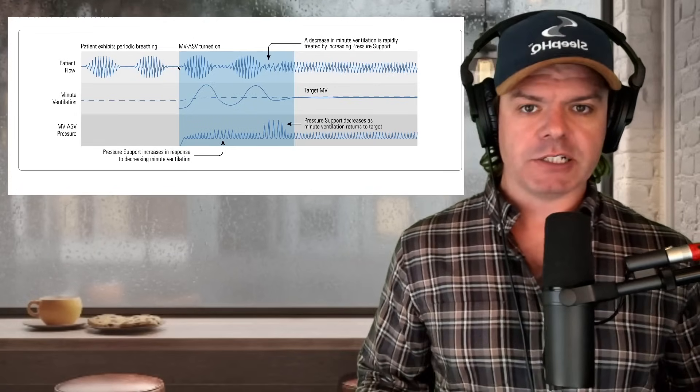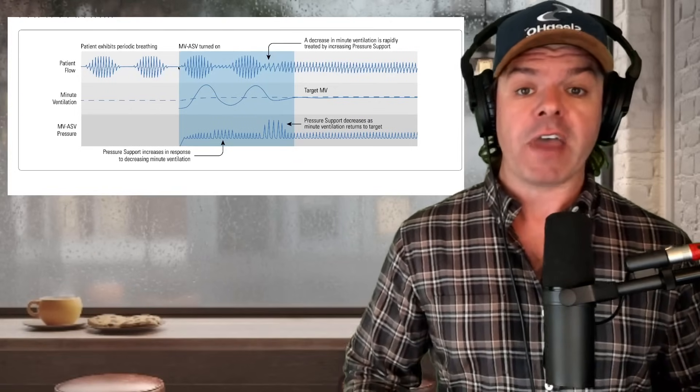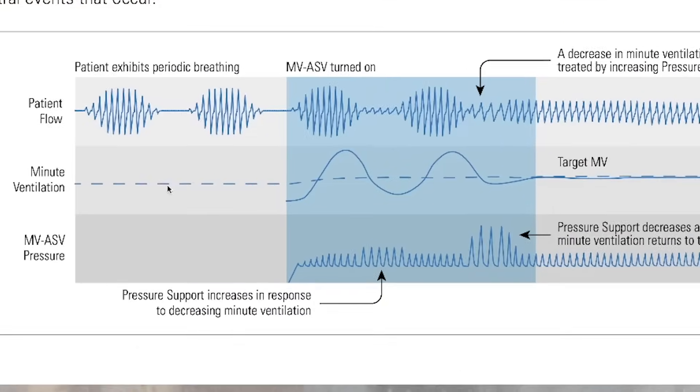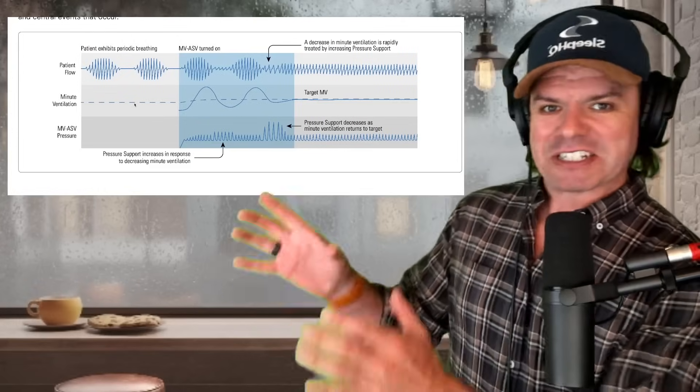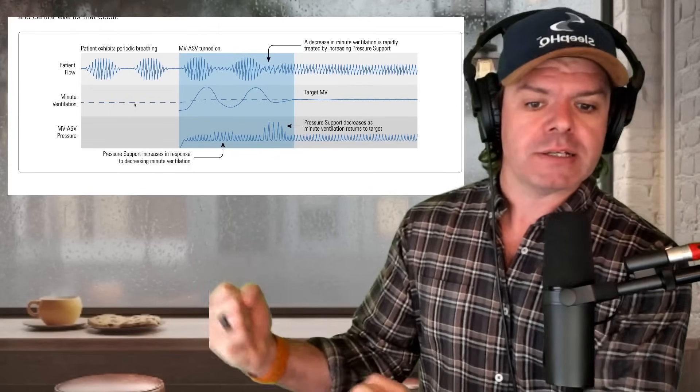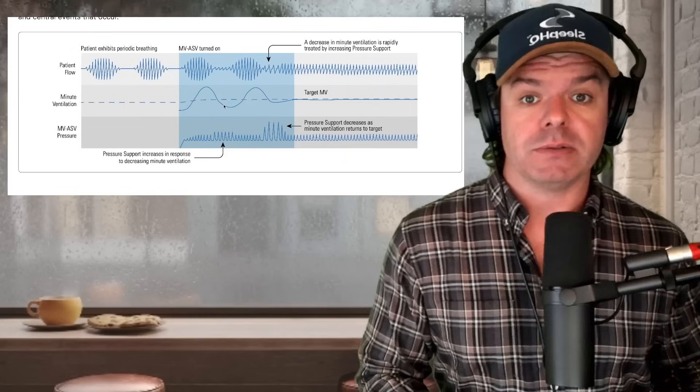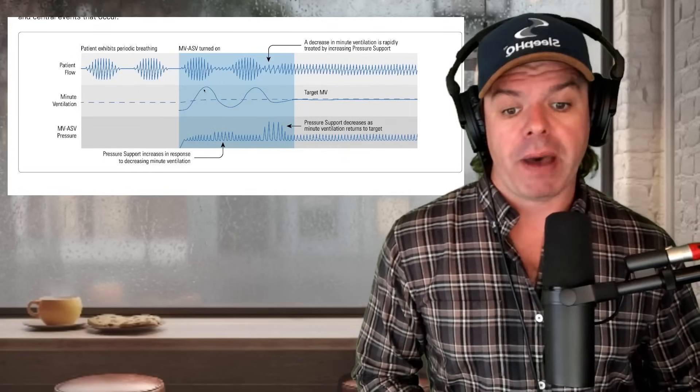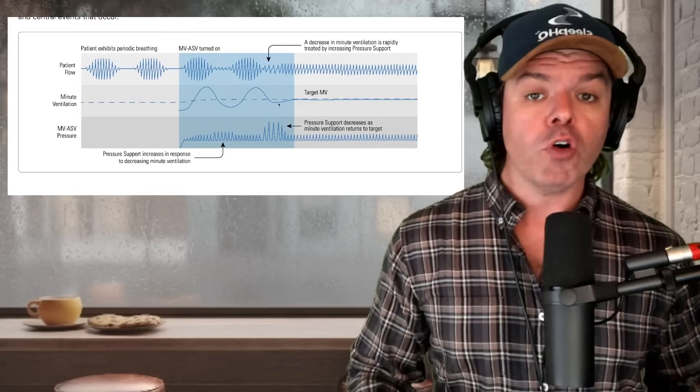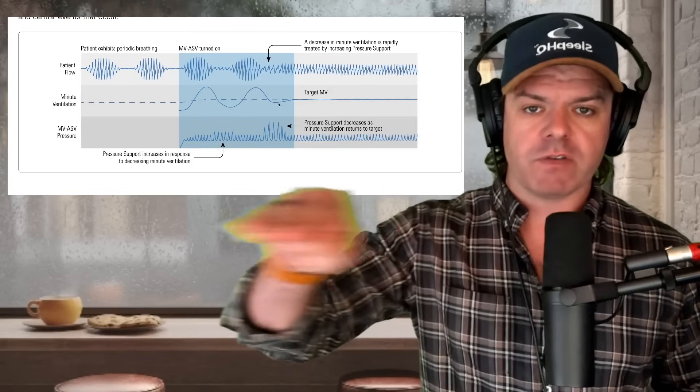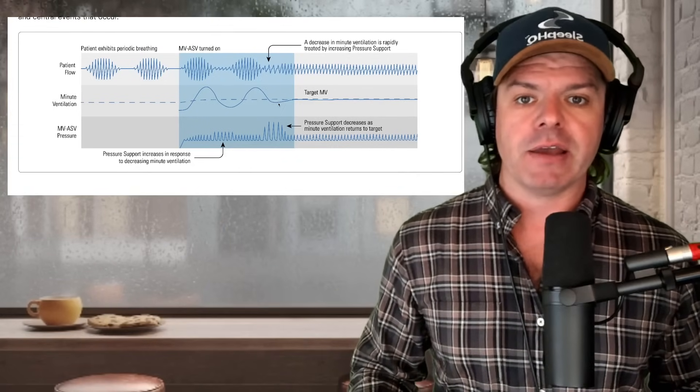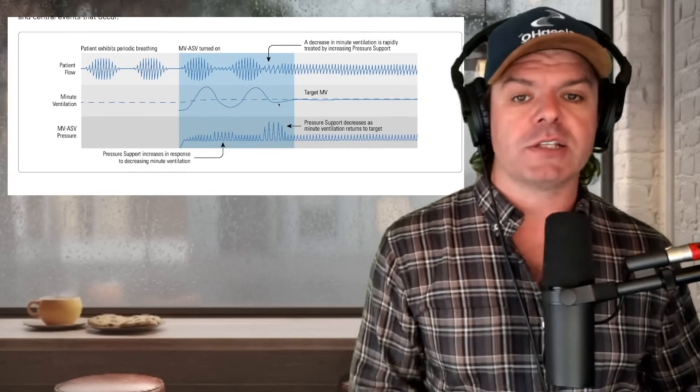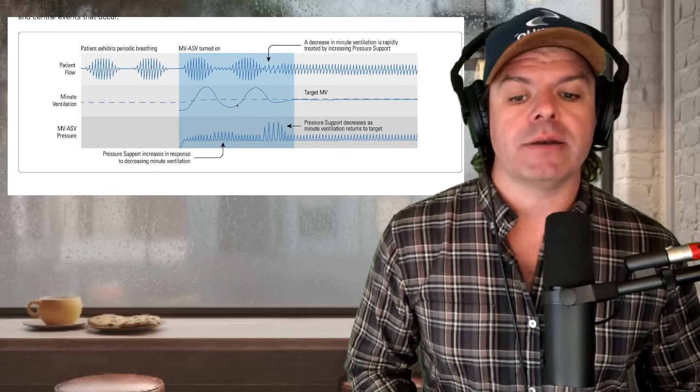Okay. Now, ASV can pick up on these patterns and it uses what's called minute ventilation to do so. Now, minute ventilation, without getting too specific, is basically the volume of air going into and out of your lungs per minute. This dashed line here is the targeted minute ventilation of the device. The device has a target, a set volume of airflow it's trying to achieve for the patient per minute. And the solid line is the patient's minute ventilation. So the machine has a target and this is the information that the patient is giving the machine, this wavy line.